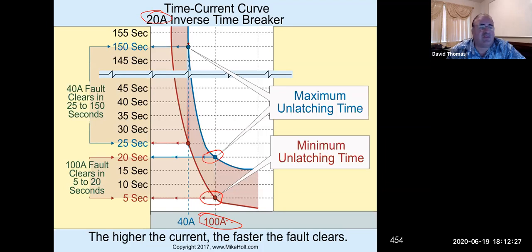And so instantaneous breakers possibly create some problems, because sometimes we do have fluctuations of current, like a motor, for example. When you start the motor, you have an inrush, then it goes down to normal current, what we call full load current in the circuit. Then we can look at, in this case, 200% or 40 amp tripping, which would have a minimum unlatching time of 25 seconds to a maximum of 150 seconds for the breaker to trip.